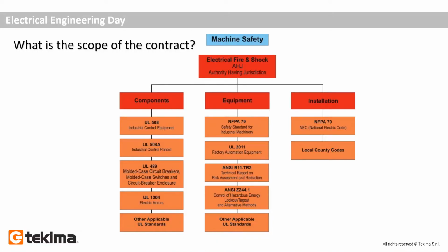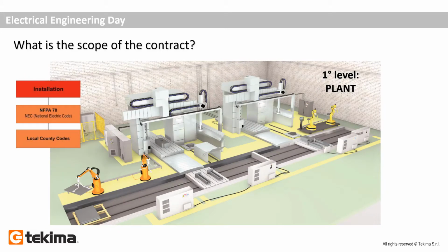As you can see on this slide, for each one of these three levels, we can have a different specific standard depending on the issues addressed. For more details on these different standards, you can refer to the presentation by C&D Consulting, which is a partner on this symposium. As we mentioned before, these are the standards for the first level, electrical installation. The most important document that we have to consider is the NEC NFPA 70 National Electric Code.